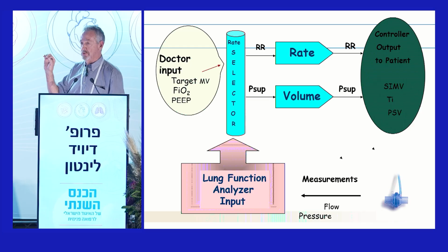What is the principle? The flow sensor in the bottom right measures those parameters. It puts it into the lung function analyzer, which has the algorithms that we wrote. It goes into a selector, and the doctor puts in the target tidal volume for the patient according to his height and weight, and the target oxygen concentration and PEEP, and the automatic controller controls only 2 parameters, rate and volume. If the patient needs a higher volume, it gives it, lower volume, it gives it, in the faster rate and lower rate. Because in certain diseases, you need a faster rate and a slower rate. And whatever you do, it gives an ideal parameter, and you get the best blood gases at the end of the ventilation.